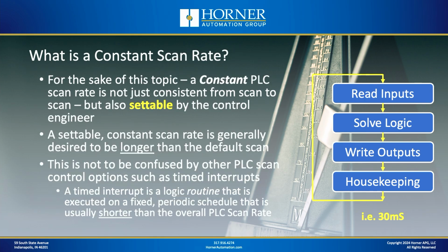All right, so again, as I hinted at when I broke down the topic today, what we're really talking about is lengthening your scan rate to a settable value. In other words, if you just let the controller do its thing, you might have a 2 or 3 millisecond scan rate, but there is some reason why you want that to be longer, say 10 milliseconds or 30 milliseconds or 50 milliseconds. Now, let's not confuse setting a longer scan rate with timed interrupts.